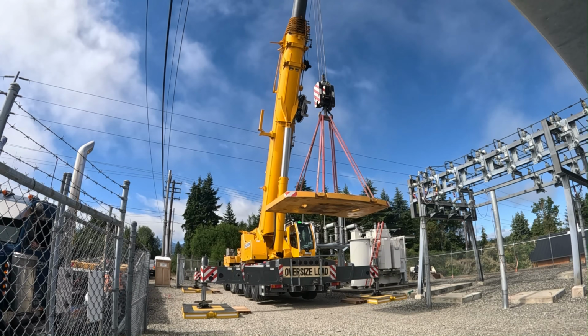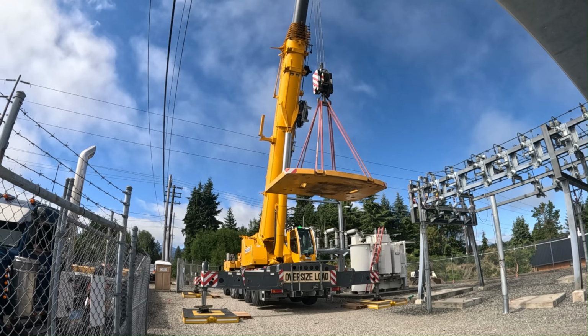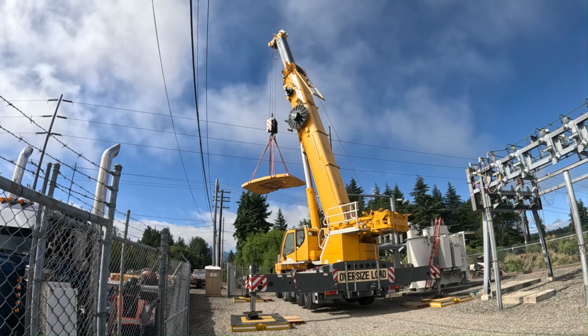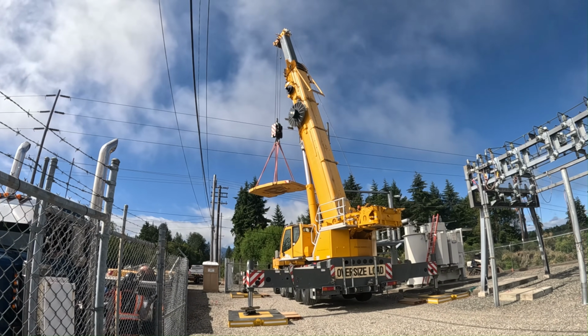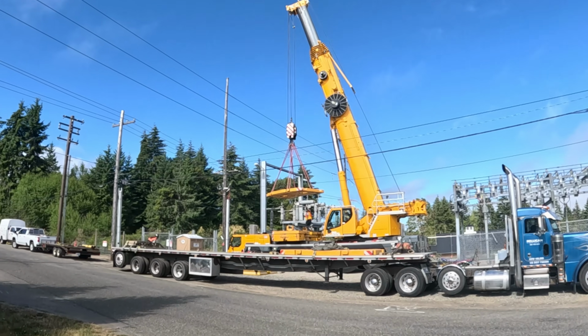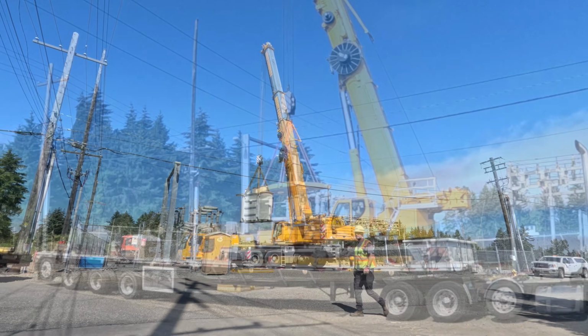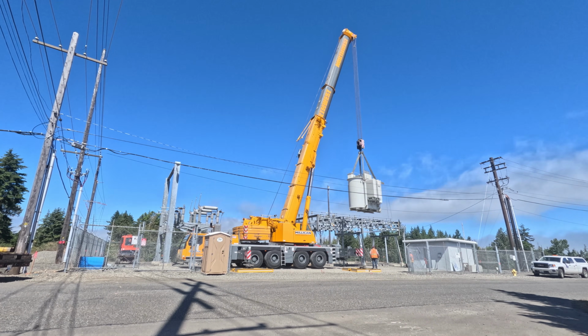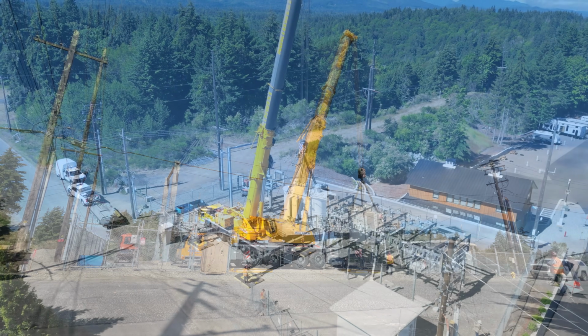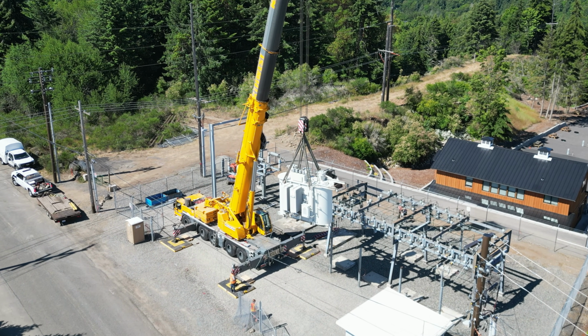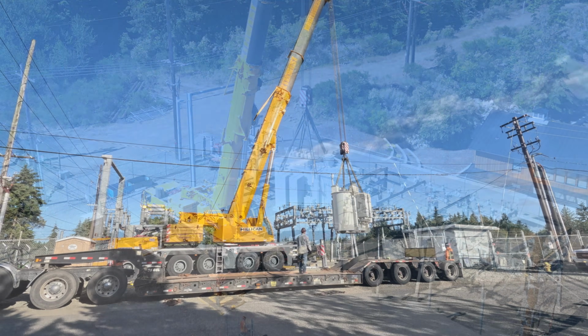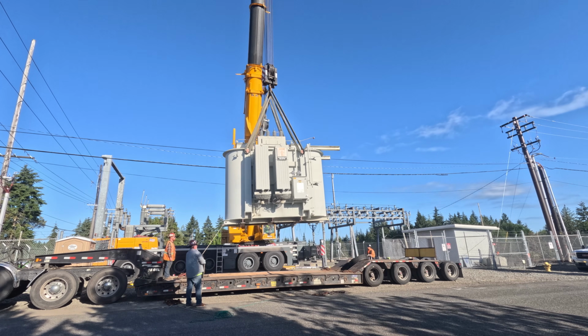A massive mobile crane is brought to the substation to lift the old transformer out. Multiple counterweights, each weighing 20 to 40 tons, are placed on the crane to counterbalance the lift. The crane is capable of lifting a maximum total weight of 275 tons, so lifting a 54-ton transformer is easy work for this impressive machine.